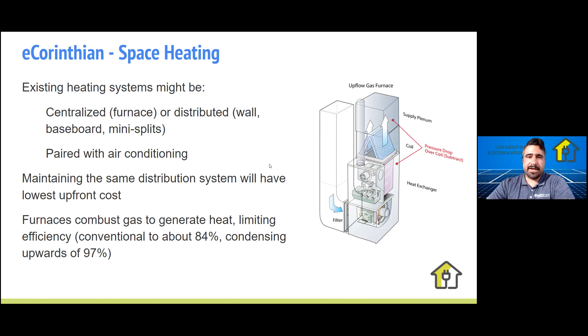In most cases what you'd be replacing is a gas furnace. Gas furnaces combust gas to generate heat — this is a conversion process, so we're limited to 100% efficiency. Conventional furnaces tend to be up to 84% efficient, while condensing furnaces reach 94-97%. But even at 97% efficient, that means 3% of the gas burned is lost, so you're still burning quite a bit of gas to supply that heat.